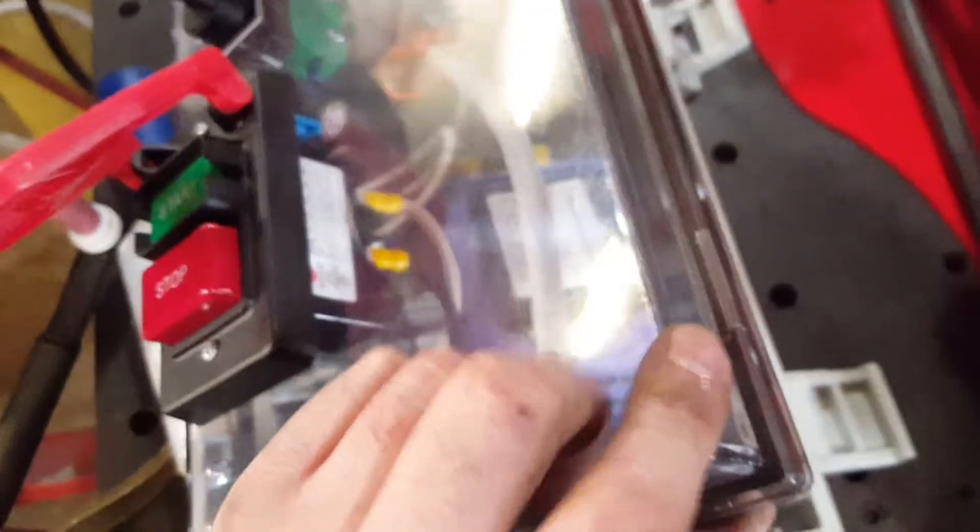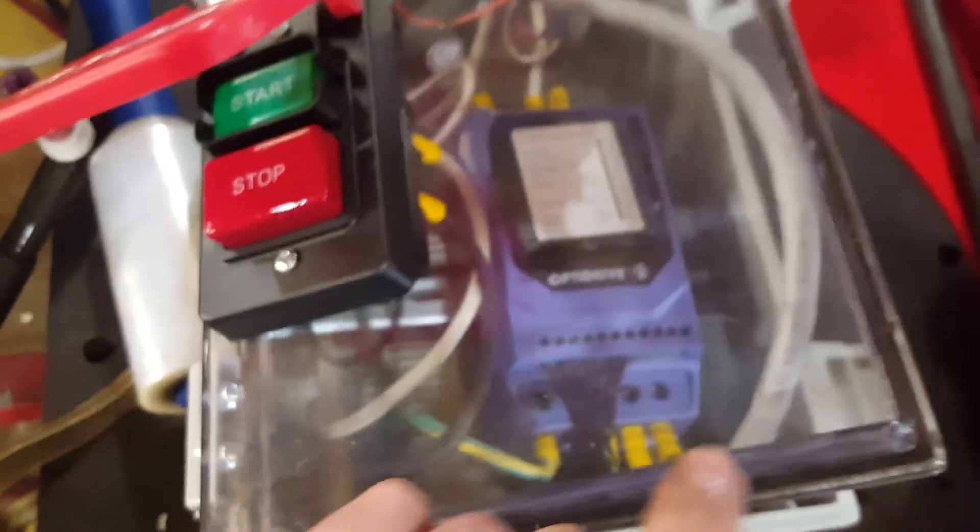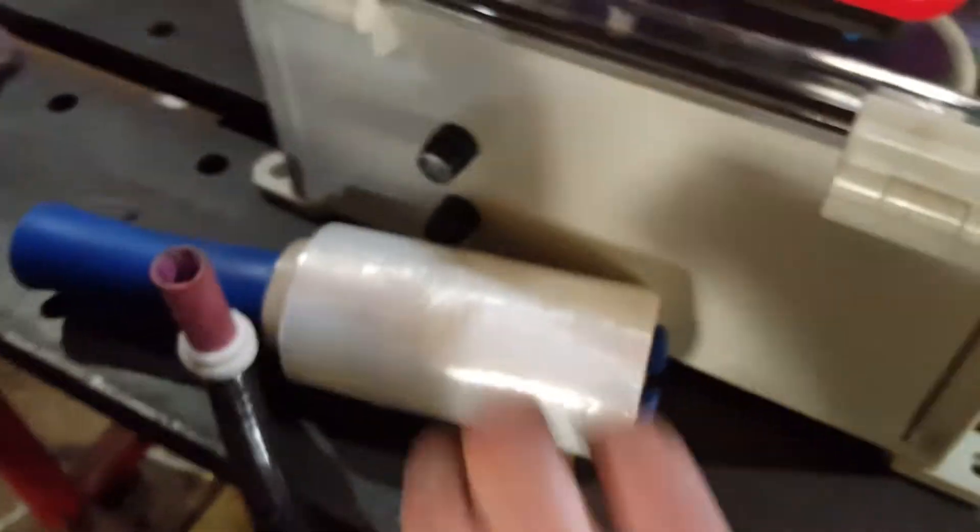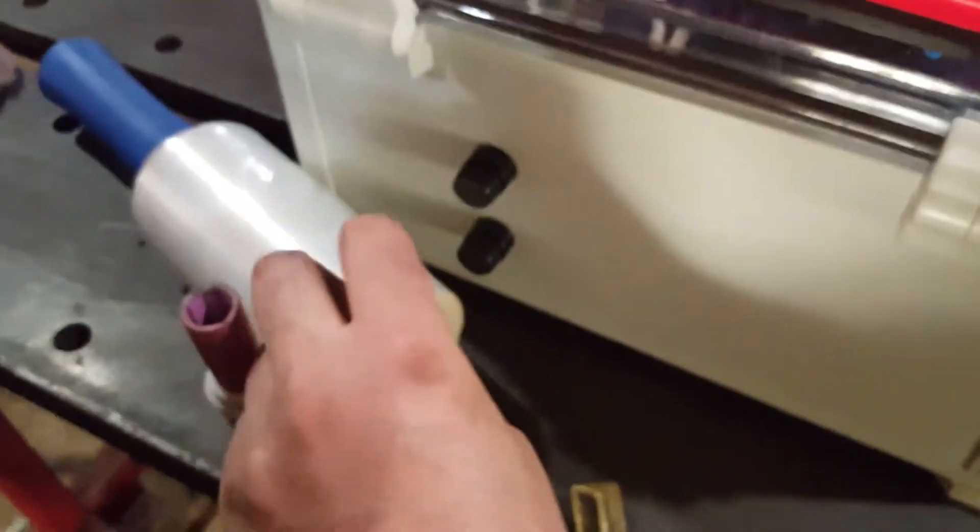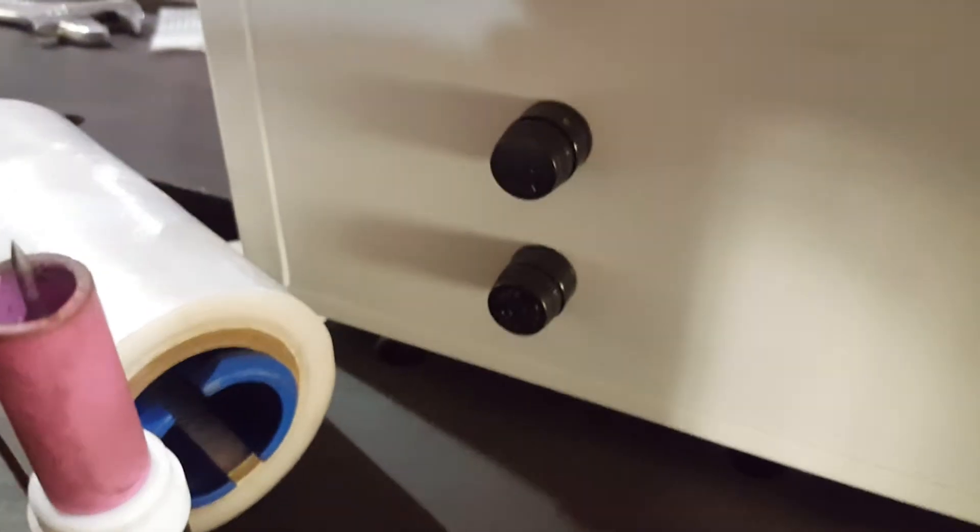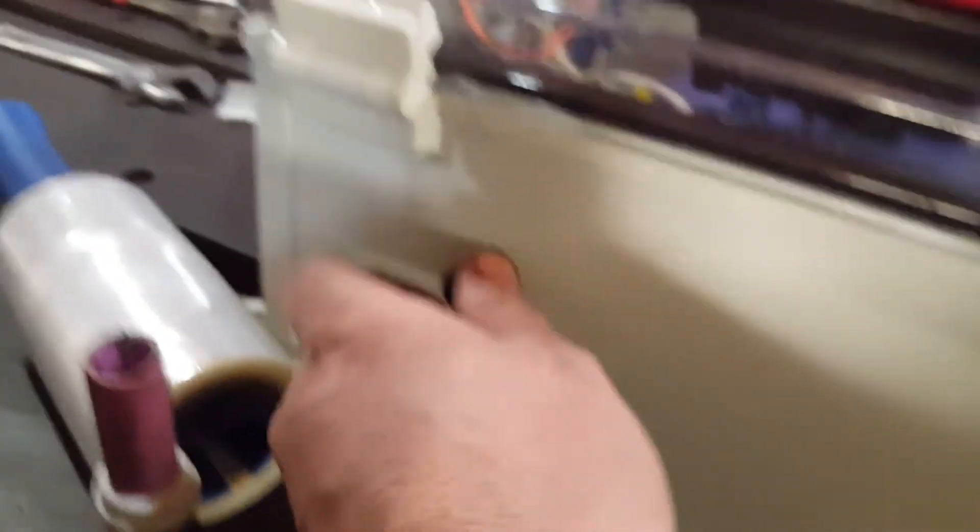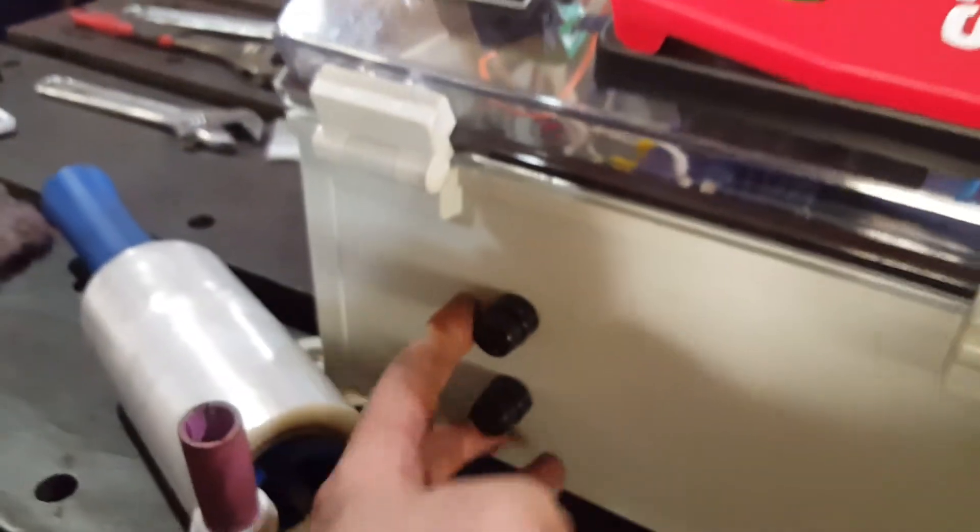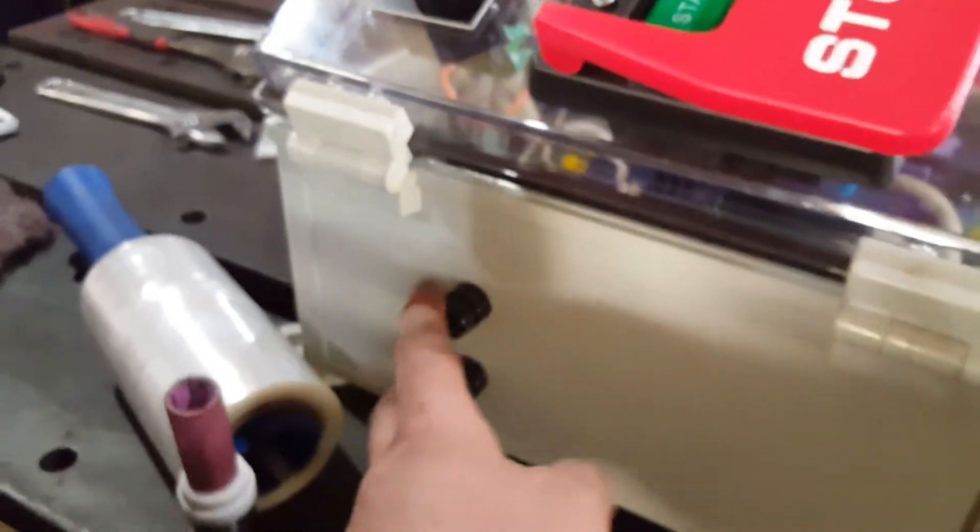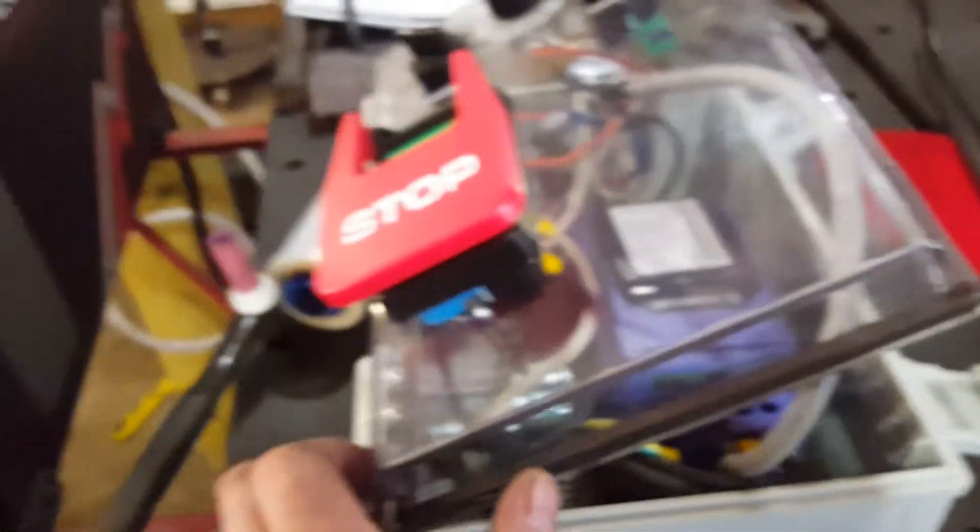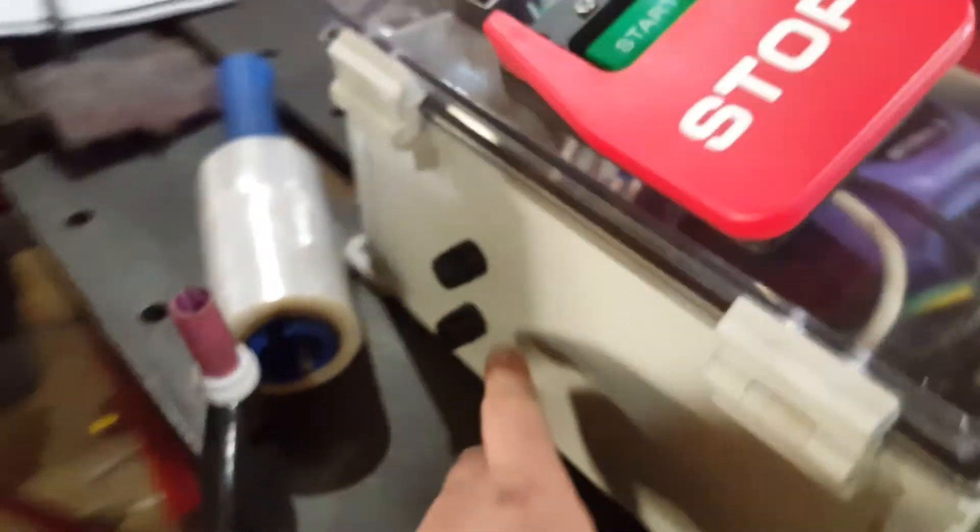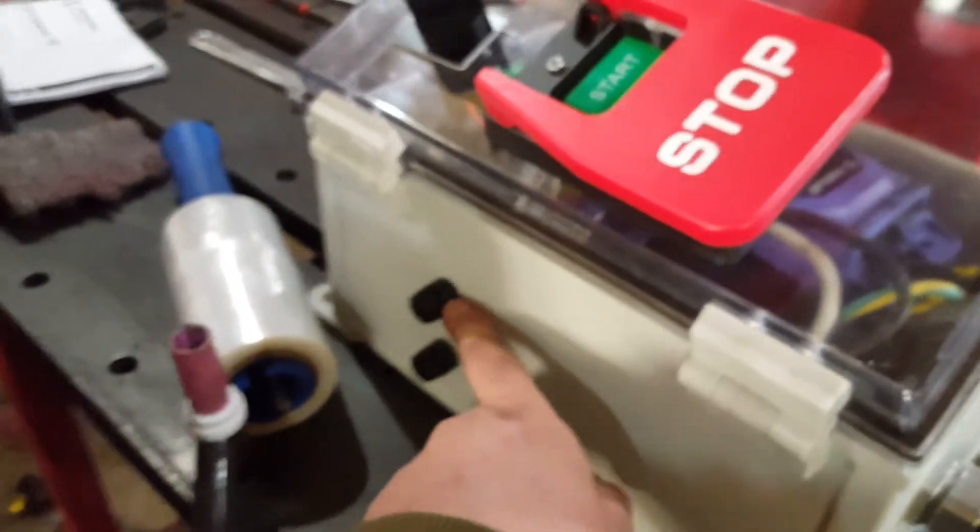Now for a two horsepower VFD, it recommends 16 amp fuses, and don't get time delay, get the fast blow fuses. I like these because they're easily replaceable from the outside, but you could use whatever you want. I'm using quarter by one and a quarter fuses, and so those are in there.